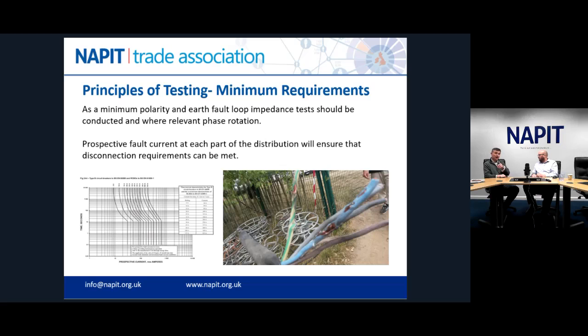And this is precisely what happened on that particular event. The cable was running across a walkway and people hadn't provided adequate mechanical protection, driving over it with their trolleys and everything. Even the rubber, although it's got good mechanical resilience, is not magic. So if you keep crushing it, it will eventually fracture. And that's what happened there. The rubber fractured, two conductors came into contact and there was a big bang. But because it wasn't an earth fault at the time, no protection worked. So it just sat there smoking and fizzing and popping. So it's important to make sure these things are thought about. Okay.